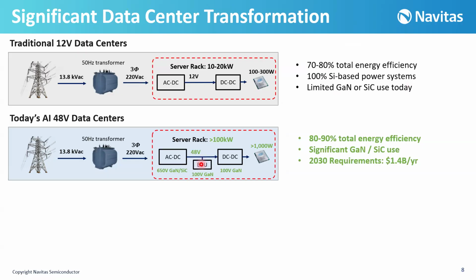I was talking about how in the second stage we step down this voltage to 48 volts, and by increasing it from 12 volts, we lower the current flow and reduce power loss. Then we convert DC-DC and power the components with more than 1,000 watts. The power density of this server rack is more than 100 kilowatts. In this architecture we use 650 volt gallium nitride and silicon carbide in the AC-DC converter, 100 volt GaN in the battery backup unit, and also 100 volt GaN in the DC-DC converter. Thanks to significant usage of gallium nitride and silicon carbide, we can now increase total energy efficiency from 70-80% to 90%. The market requirement by 2030 is 1.4 billion per year.